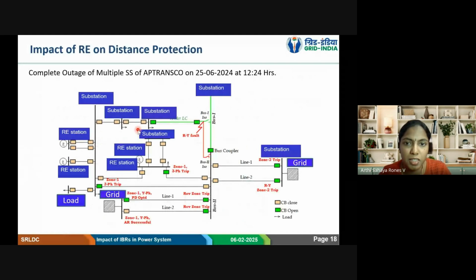So the case study, I would like to present one event that happened in AP. There were multiple outages of substations on 25th June. So here, this is a grid connecting substation. There are two grid connections here, one grid and two. And this portion is completely radial because here we have only the RE station and there is a load. And during the antecedent, this particular line, this substation to this station line, was under open condition. So this whole thing was radial.